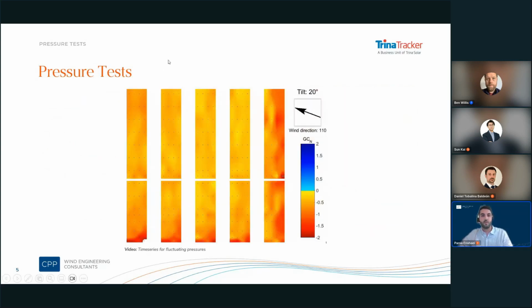Cool, so here's a video of pressures measured on 5 rows of trackers in a generic rectangular array. As you can see on the top right, the wind is coming from the bottom right-hand side of the page, and these trackers are tilted at positive 20 degrees. So in the first row, at the leading edge, that will be pointing upwards. Your uplift, the pressure trying to pull the panel away from the ground, is really your key design wind load here.